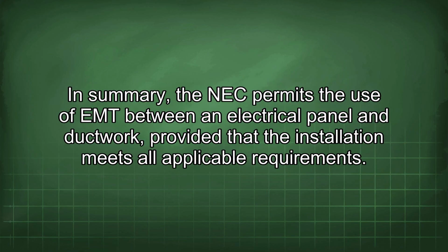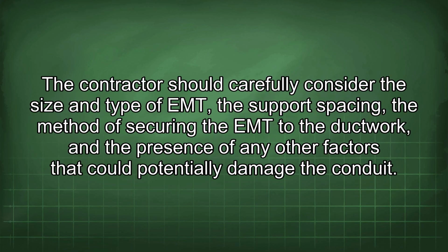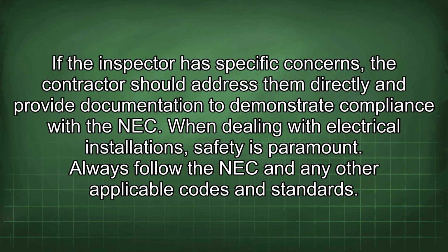In summary, the NEC permits the use of EMT between an electrical panel and ductwork, provided that the installation meets all applicable requirements. The contractor should carefully consider the size and type of EMT, the support spacing, the method of securing the EMT to the ductwork, and the presence of any other factors that could potentially damage the conduit. If the inspector has specific concerns, the contractor should address them directly and provide documentation to demonstrate compliance with the NEC.